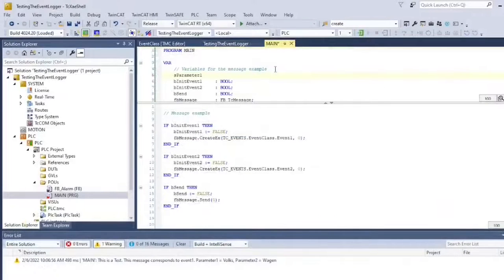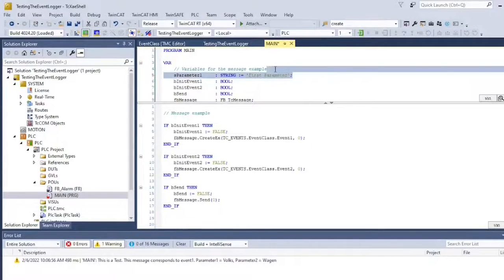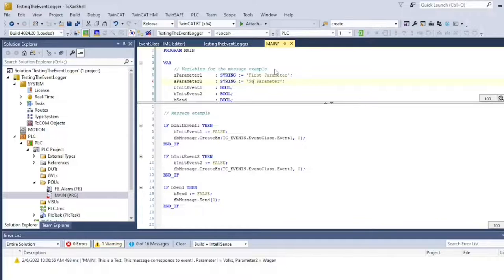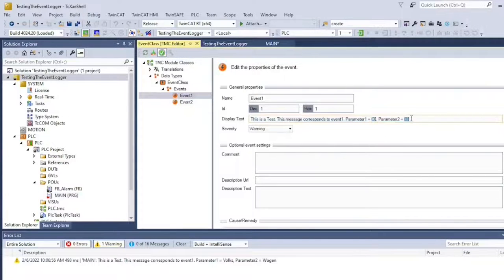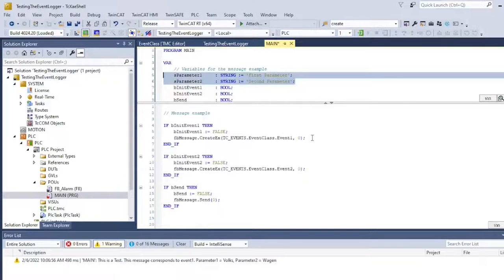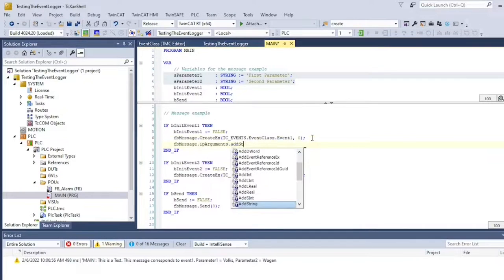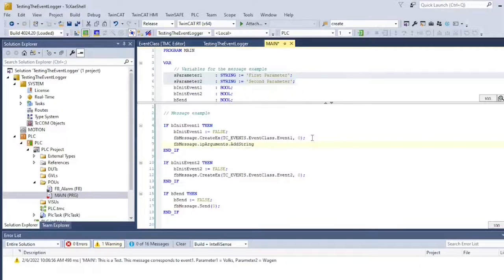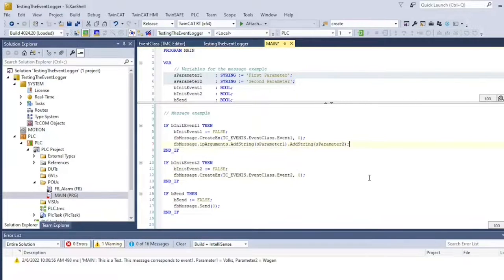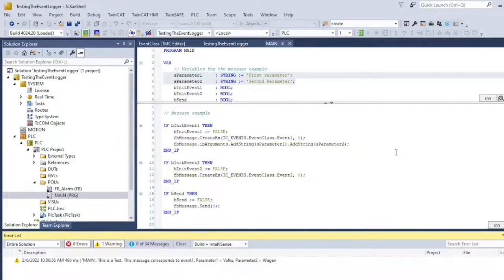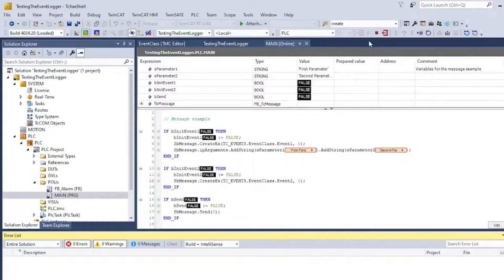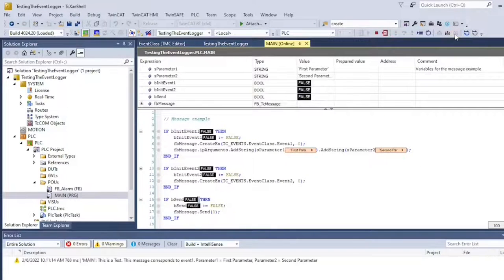Now let's see how to parameterize a message. First declare your parameters, they don't need to be strings as we'll see in a second. We need to change the definition of the event and include placeholders for these parameters. Then call the method addString through the IP arguments interface pointer passing your parameters. Rebuild your solution and download it to the controller. Now your messages can be customized.